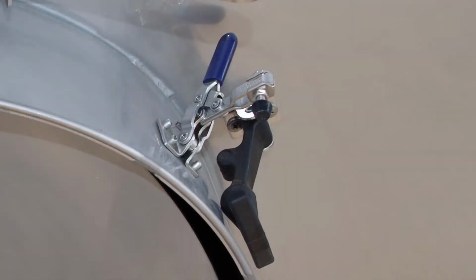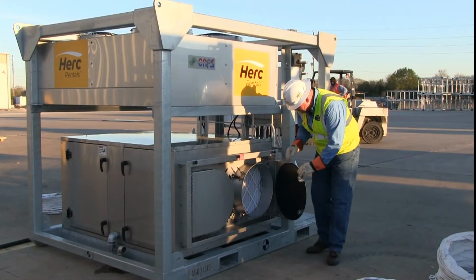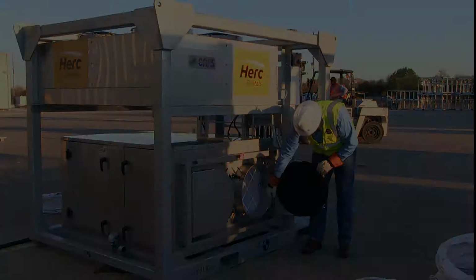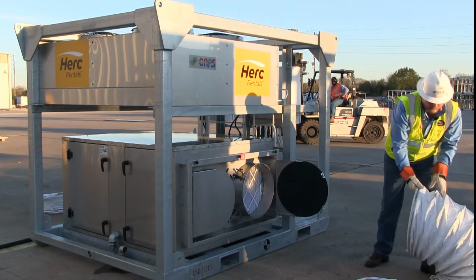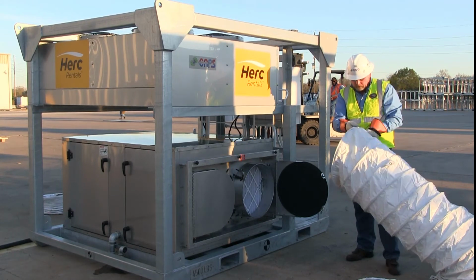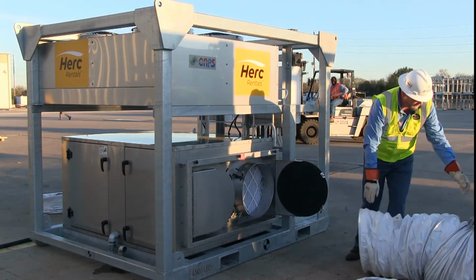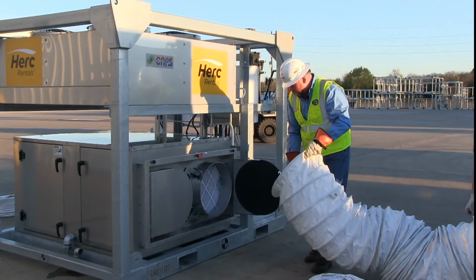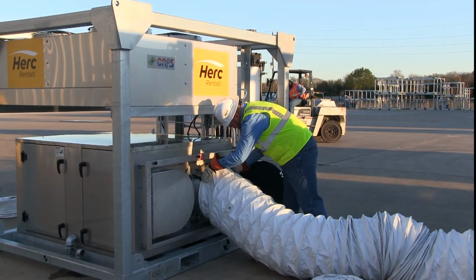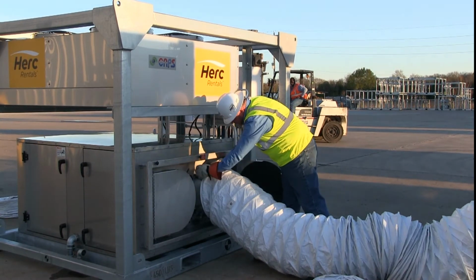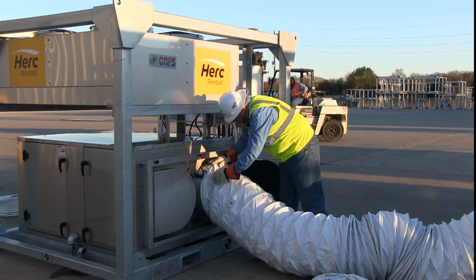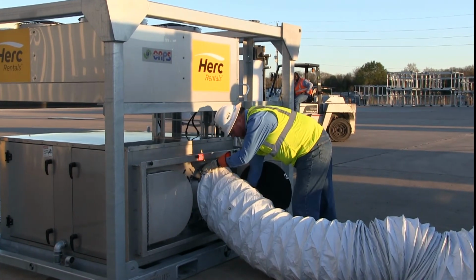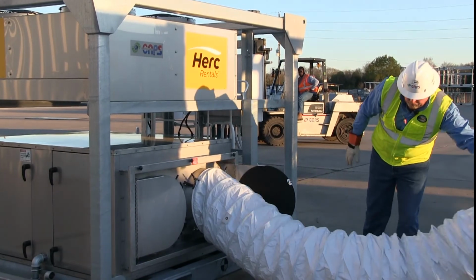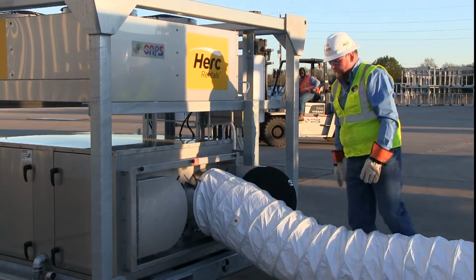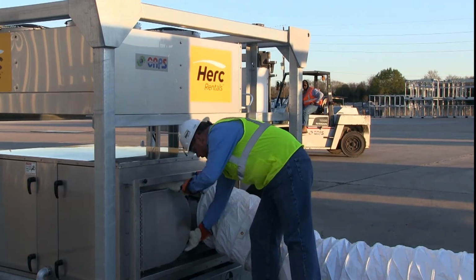We have these Jeep latches here that hold the duct caps closed. As it comes over, there's a pull pin down here, and you're going to take the ductwork, and all the ductwork is marked with a direction of airflow arrow on there. So we're going into the unit. You simply hook up the ring to the inlet of the unit, the intake. You're going to lock down the 4 friction clamps that secure the ductwork in place, and then this can be pulled out and taken to the area that the ductwork's going to serve. The 20-ton unit has 2 intakes on it. Very simple to hook it up.